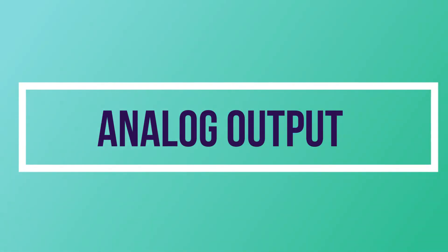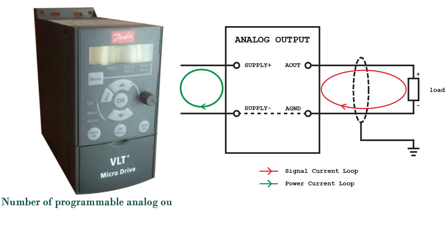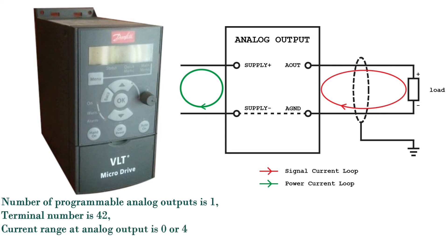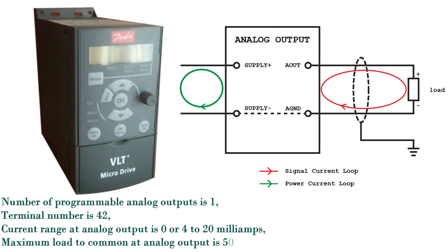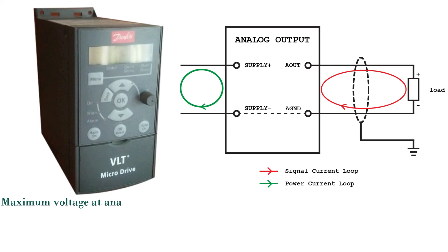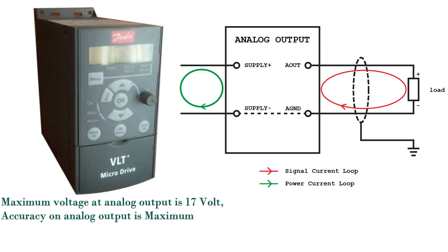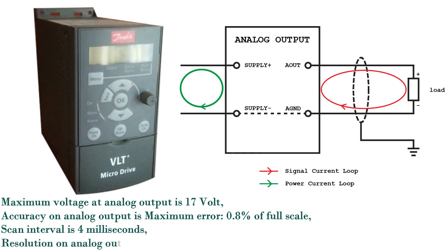Analog output: number of programmable analog outputs is 1; terminal number is 42. Current range at analog output is 0 or 4 to 20 milliamps. Maximum load to common at analog output is 500 ohm. Maximum voltage at analog output is 17 volt. Accuracy on analog output is maximum error 0.8% of full scale. Scan interval is 4 milliseconds; resolution on analog output is 8 bit.